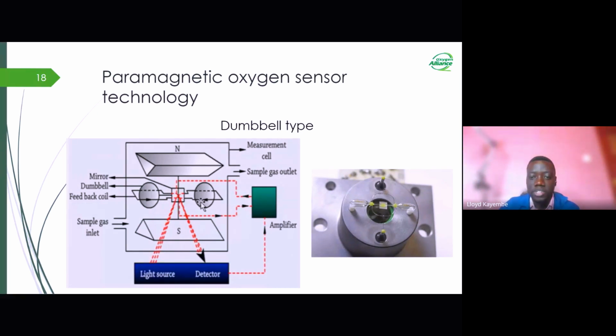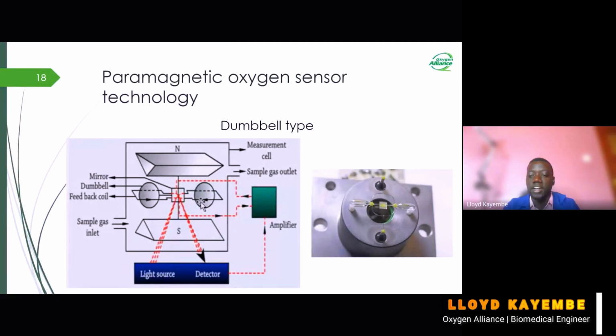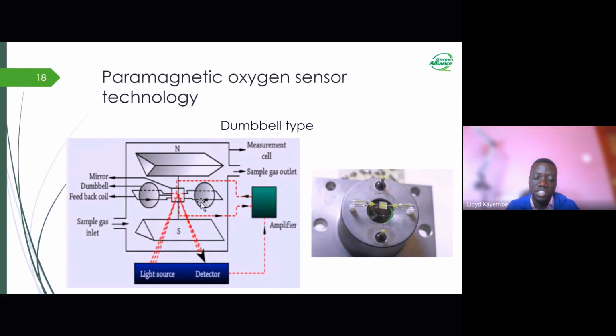In the dumbbell type, the sensor contains a permanent magnet, and in between the magnets, there's an assembly of 2 nitrogen glass spheres surrounded by feedback or compensation coils. These spheres are mounted on a rotating suspension. The feedback coils on the spheres also generate a magnetic field that interacts with the magnetic field of the permanent magnet, making a delicate balance of the rotating suspension. There's also a mirror fixed between the sphere suspension, such that when the sphere suspension assembly rotates, the mirror also rotates. There's a light source directed onto the mirror, and a photodetector onto which the reflection of the light is directed. The whole sensor unit is enclosed and has an outlet and an inlet.